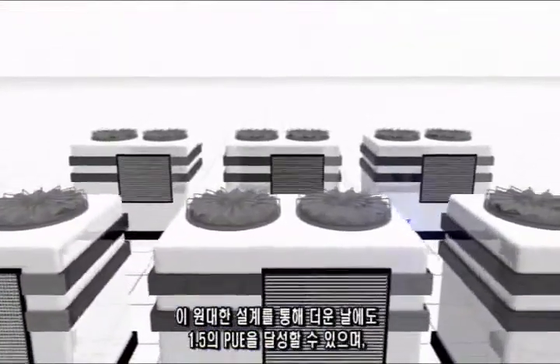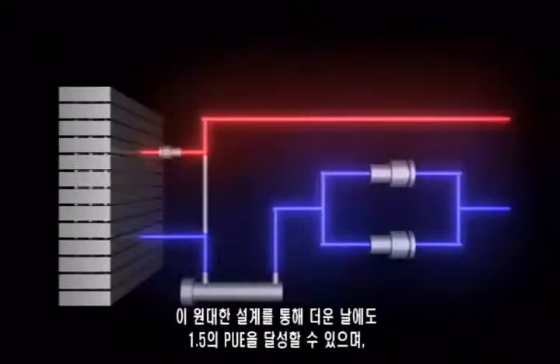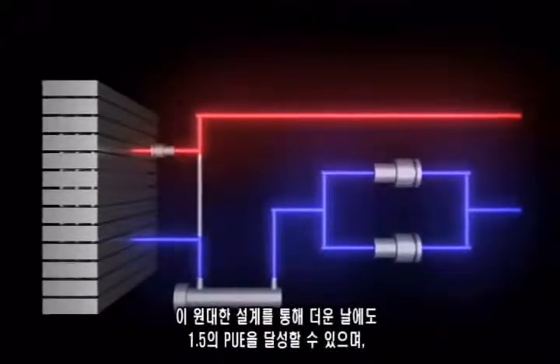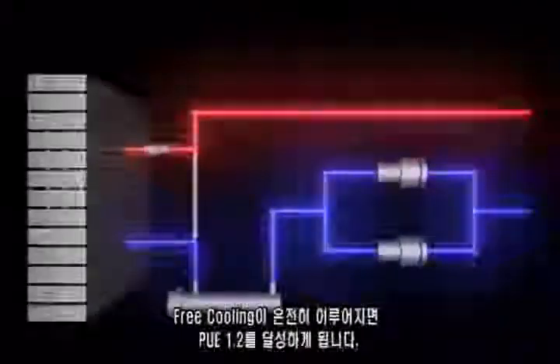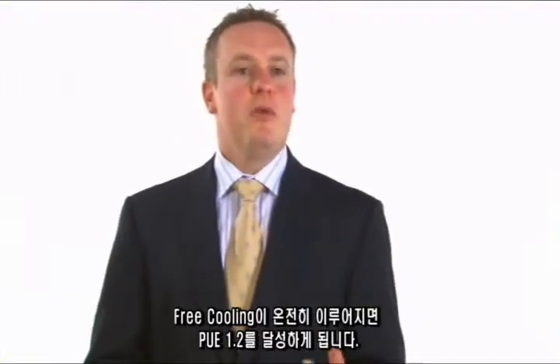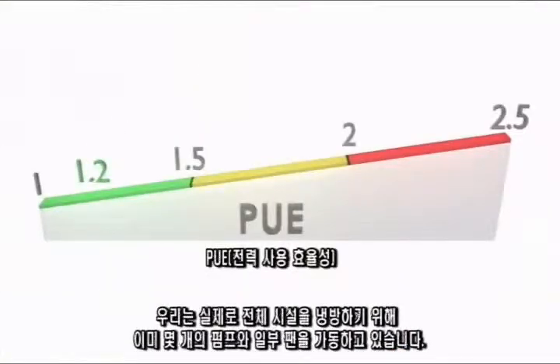With our green design, even on a hot day, we should be achieving a PUE of 1.5, and once the free cooling kicks in completely, we should be achieving a PUE of 1.2, because we're really only running a couple of pumps and some fans to actually cool the entire facility.